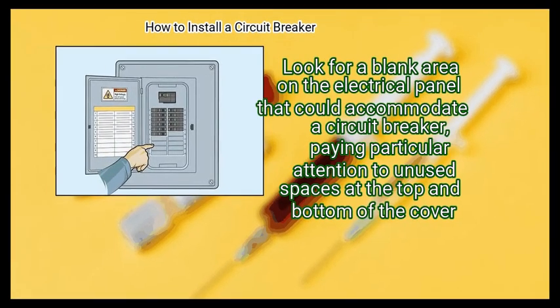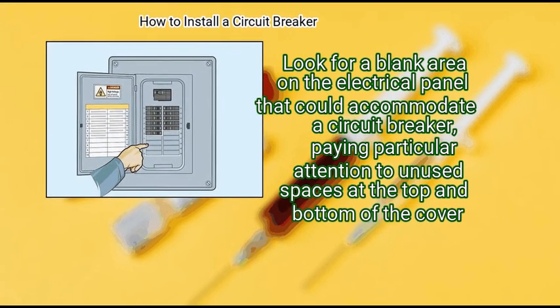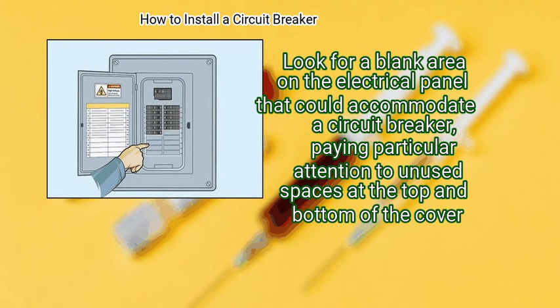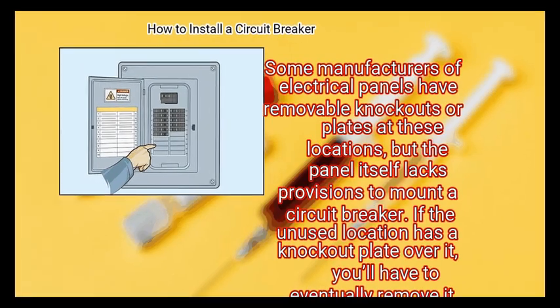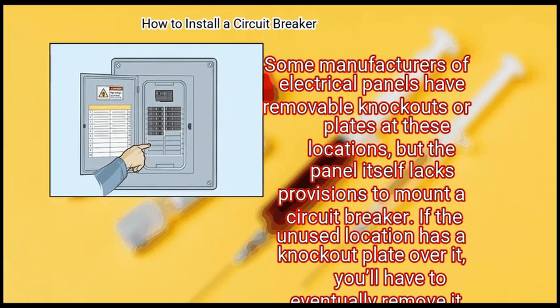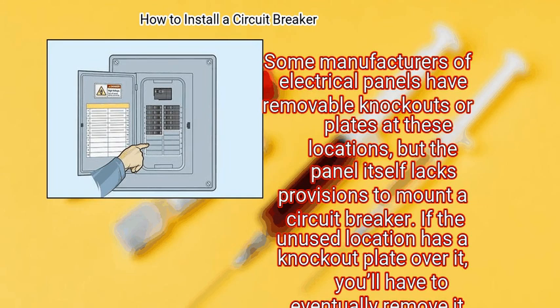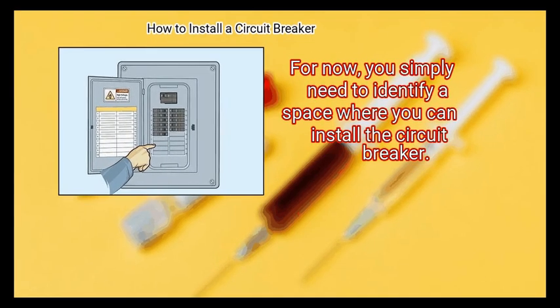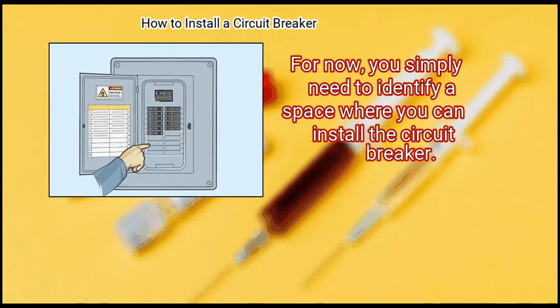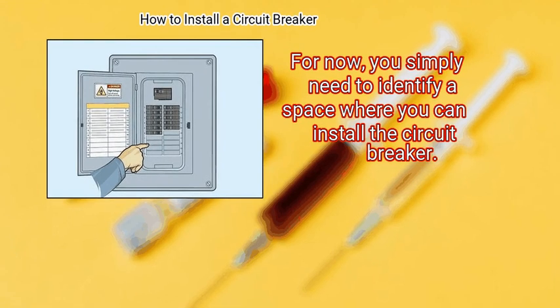Look for a blank area on the electrical panel that would accommodate a circuit breaker, paying particular attention to unused spaces at the top and bottom of the cover. Some manufacturers of electrical panels have removable knockouts or plates at these locations, but the panel itself lacks provisions to mount a circuit breaker. If the unused location has a knockout plate over it, you'll have to eventually remove it before completing the installation process. For now, you simply need to identify a space where you can install the circuit breaker.